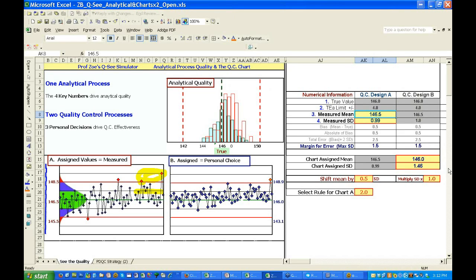But it seems to me that if some samples have unexpectedly started to shift higher or lower, that is telling you that there's something wrong, and to just shift your curve to accommodate that change is, as was just previously mentioned, it would seem to me to be a very dangerous thing to do.